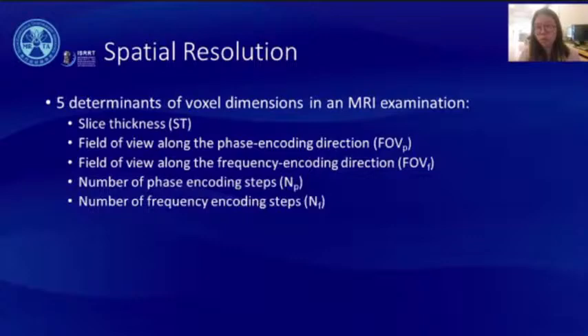So, high spatial resolution is used for small lesion detection and shape assessment. How can we increase spatial resolution? There are 5 determinants of voxel dimension in an MRI examination. Alteration in any of these 5 parameters will change the voxel volume. Alterations in the number of phase encoding steps affect scan times, while alterations in the number of frequency encoding steps may affect the maximum number of slices as well as the minimum possible TE for the imaging sequences. Voxels that are too large for the anatomic structures being examined cause the viewer to observe what is perceived as blurriness in the image, while decreasing the size of the voxels has the potential to increase the sharpness of the image, but decrease in SNR.